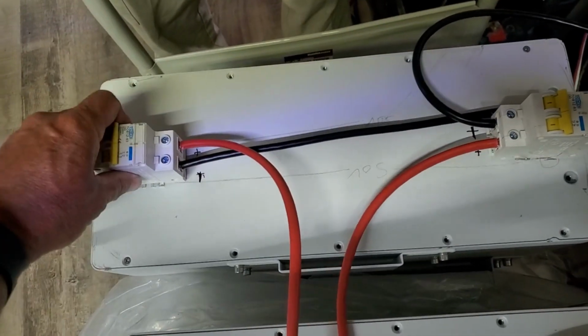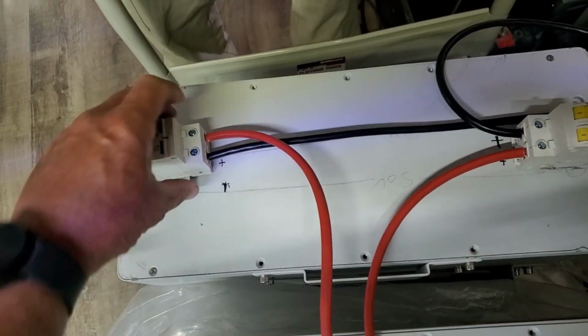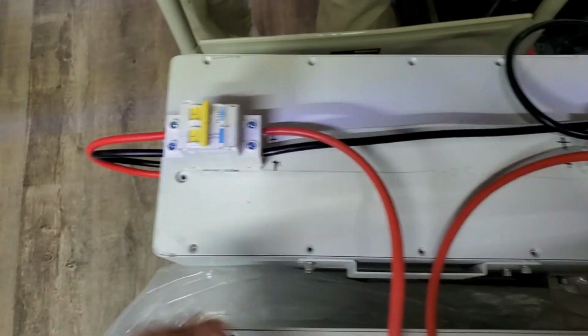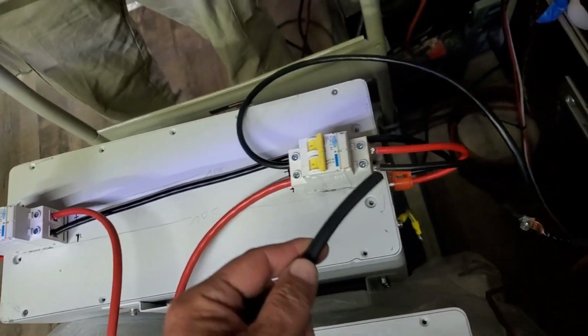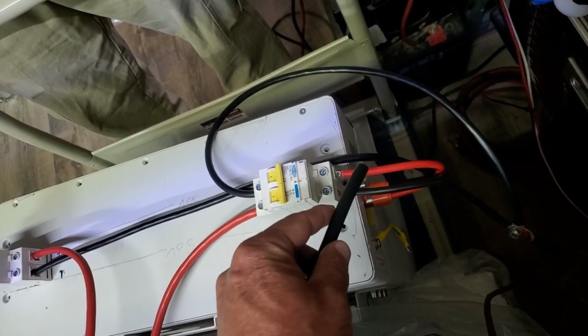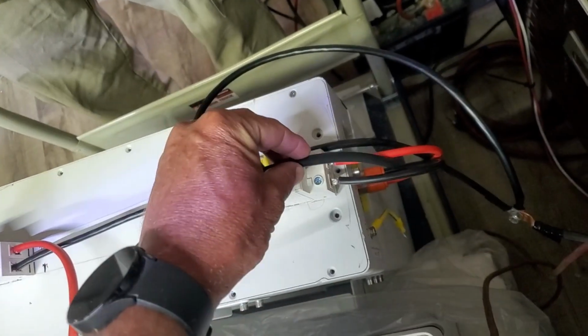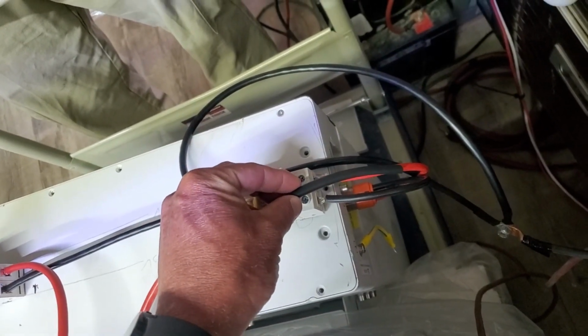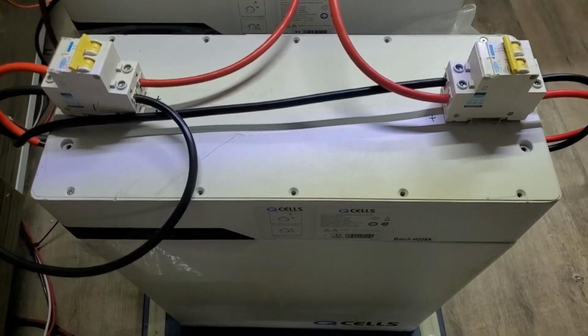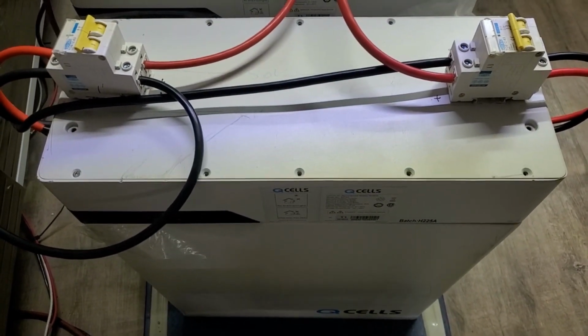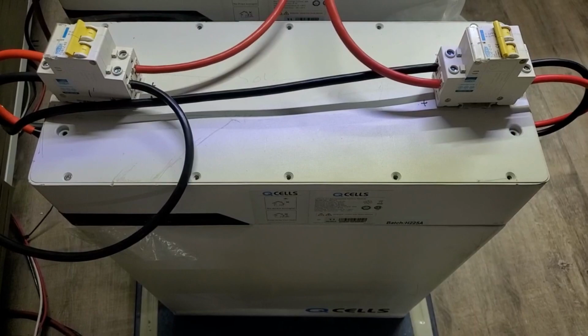So this kit will include the two breakers, the DIN rail to mount on the unit, the connectors on the back over here, and two pieces of heat shrink, because the wires on this side over here are the wrong polarity. So this will have to be black over here. I'm going to slide this piece of heat shrink over there. So there you have a 6.4 kilowatt hour battery for just under 1200 bucks.